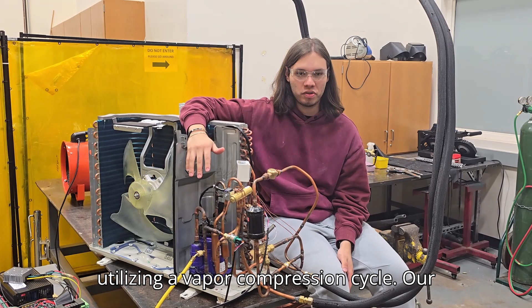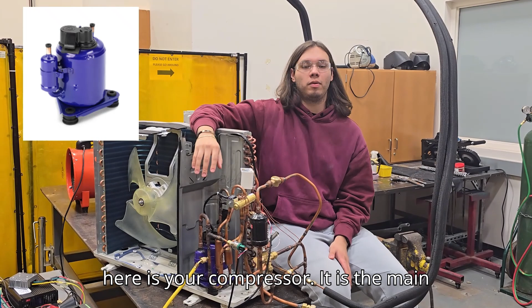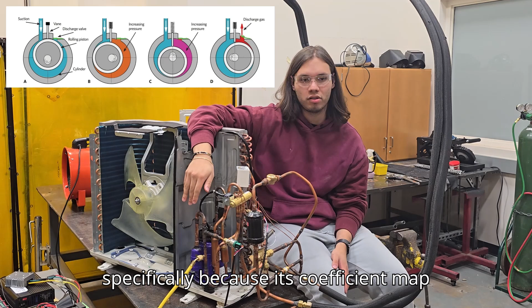Our system will be charged with refrigerant R1234yf, primarily because of its low GWP of 4. This right here is our compressor. It is the main component of the vapor compression cycle, and it'll consume about 80% of the entire system's power. It is a rotary style compressor and was picked specifically because its coefficient map showed a 1 ton refrigerant capacity, and it also runs directly on DC power.